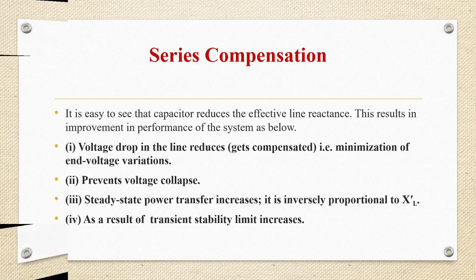So first point is that capacitor will reduce the effective line reactance, and what is happening because of this? So improvement in performance of the system as below. First one is voltage drop in the line will reduce and will get compensated, or that is minimization of end voltage variations. Second one is it will prevent voltage collapse. Third one is steady state power transfer will increase and it is inversely proportional to XL dash. So as a result of transient stability limit will increase.